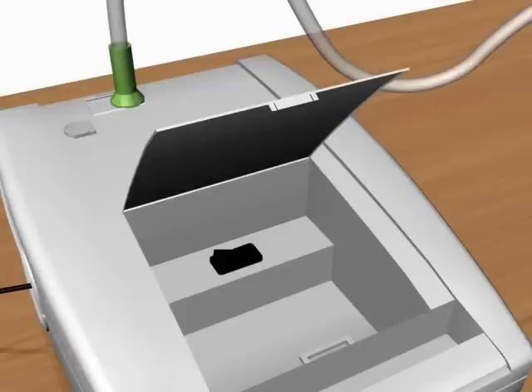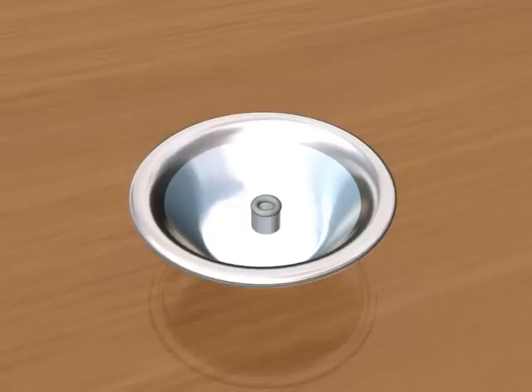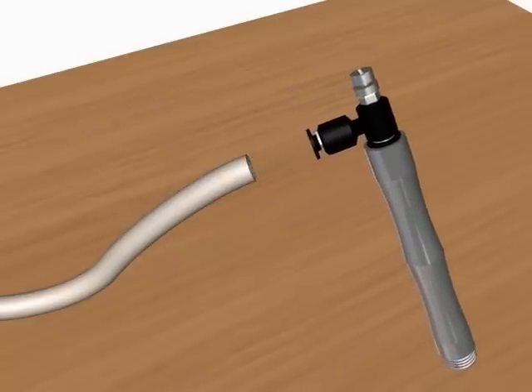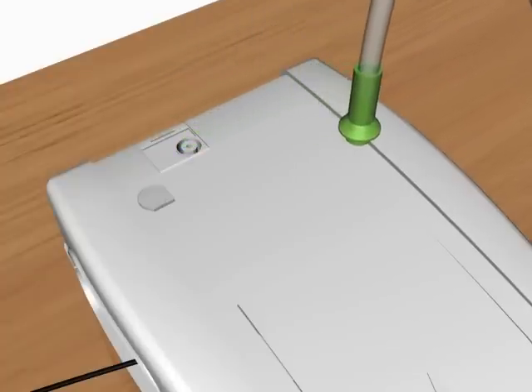After the completion of the process, switch off the machine and remove the diamond. Clean the diamond with the brush and keep it in boiling water for sterilization. Now press the push button to unlock the connector tube from the one piece handle. After that, remove the other end of the connector tube from the inlet of the machine.